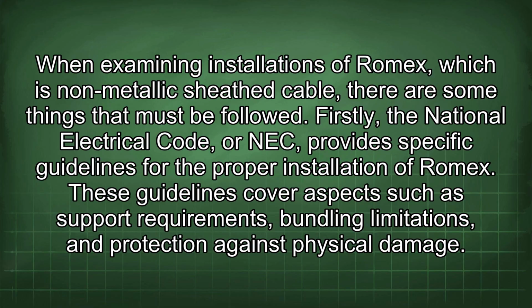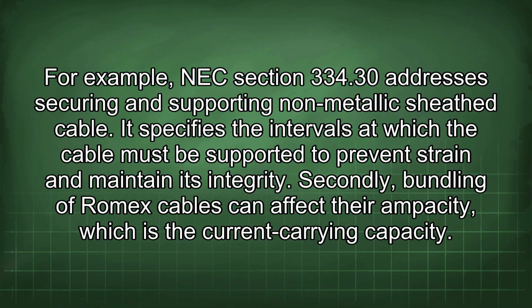be followed. Firstly, the National Electrical Code, or NEC, provides specific guidelines for the proper installation of Romex. These guidelines cover aspects such as support requirements, bundling limitations, and protection against physical damage. For example, NEC Section 334.30 addresses securing and supporting non-metallic sheath cable. It specifies the intervals at which the cable must be supported to prevent strain and maintain its integrity.